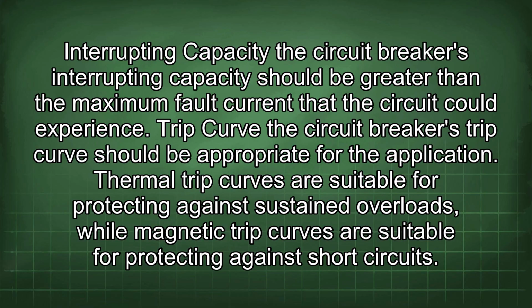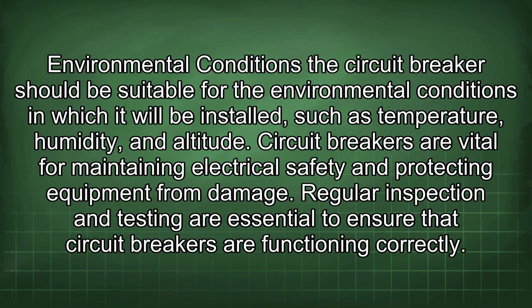Thermal trip curves are suitable for protecting against sustained overloads, while magnetic trip curves are suitable for protecting against short circuits. Environmental conditions. The circuit breaker should be suitable for the environmental conditions in which it will be installed, such as temperature, humidity, and altitude. Circuit breakers are vital for maintaining electrical safety and protecting equipment from damage. Regular inspection and testing are essential to ensure that circuit breakers are functioning correctly.